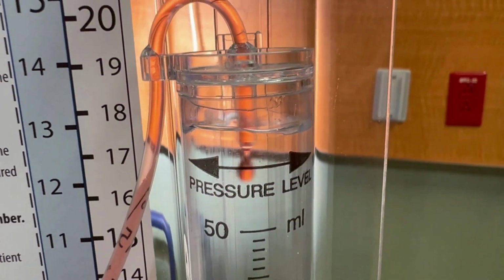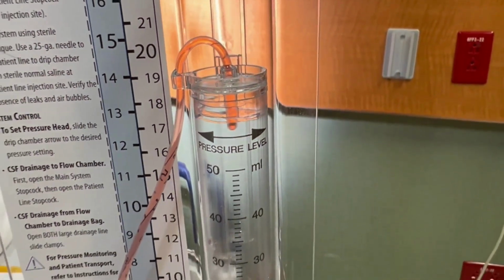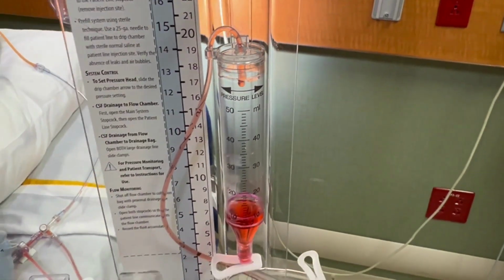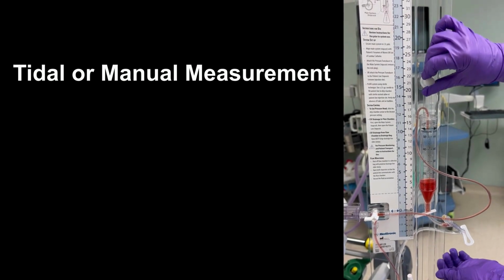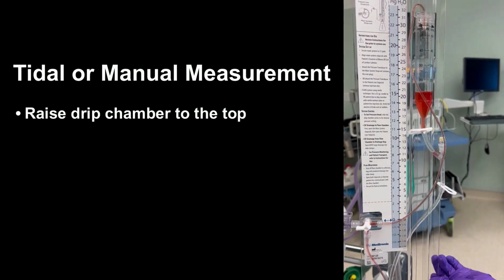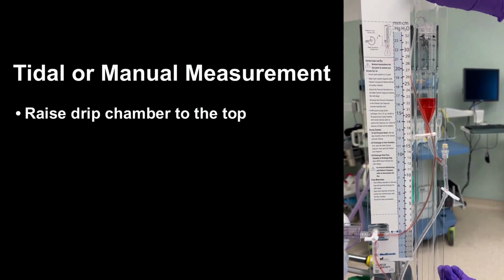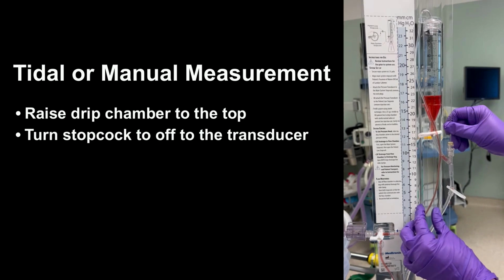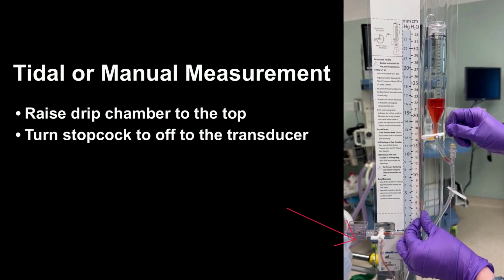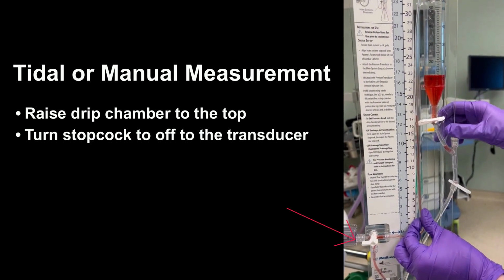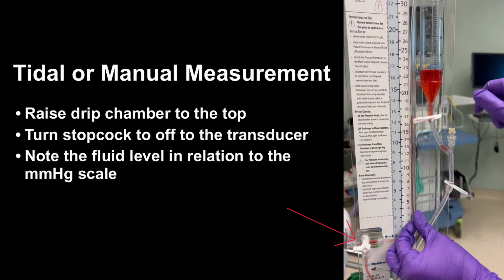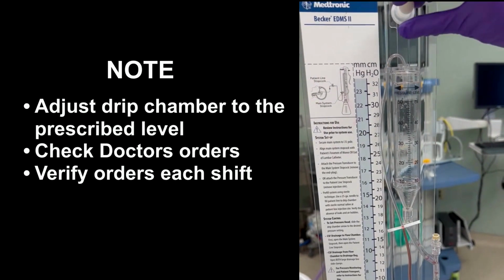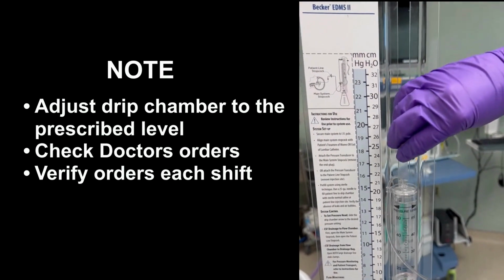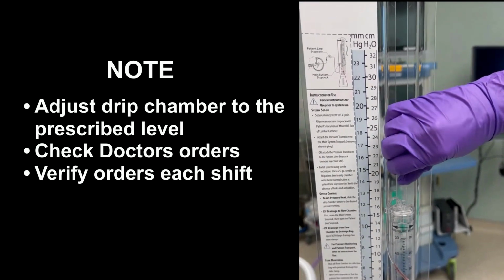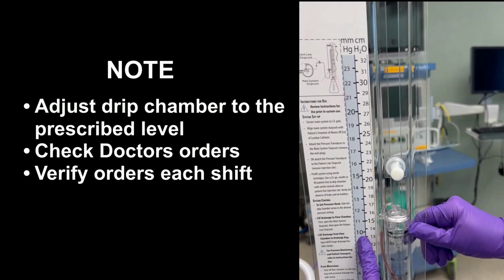Don't forget to return the drip chamber to the prescribed level prior to opening the stopcock to drain. To obtain a tidal measurement, also referred to as a manual measurement, raise the drip chamber to the highest setting using the flow chamber locking bracket. Then turn the main system stopcock to off to the transducer. Note the fluid level inside the tubing in relation to the scale on the system. Adjust the drip chamber to the prescribed level, ensuring the system is either off or open per the provider's order. Make sure you verify this order each shift.